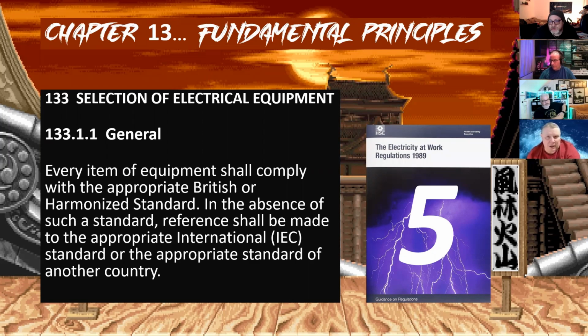He had a residual current monitor on there. He was trying to get ADS in the traditional fashion. He's saying, but my earthing impedance is too high. What is the fundamental design? What is the fundamental means of protection that's been designed into that installation? That information didn't get to him, so he just didn't know how to inspect and test because he didn't have it.